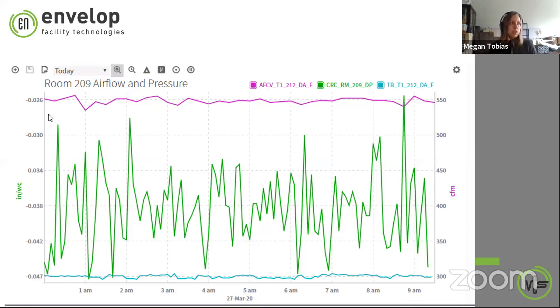This is actually one of the rooms that was already an isolation room. It's got your supply airflow down on the bottom in blue, and your return airflow up top in pink. You want your return to be higher than your supply, because that causes your negative pressure, shown in green. You can see how it fluctuates as the airflow fluctuates, or as people open the door to go in or out.